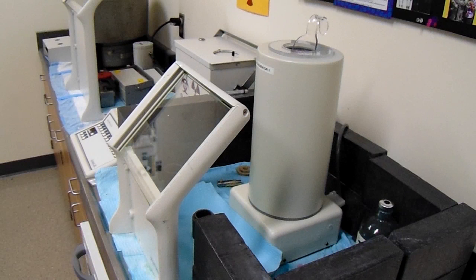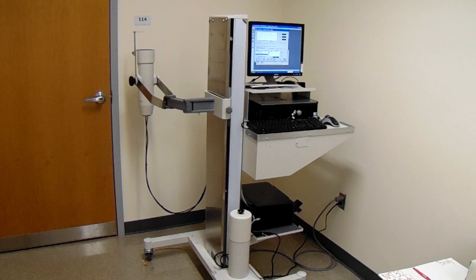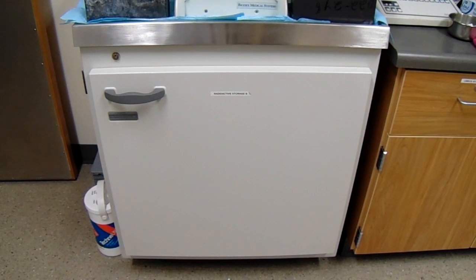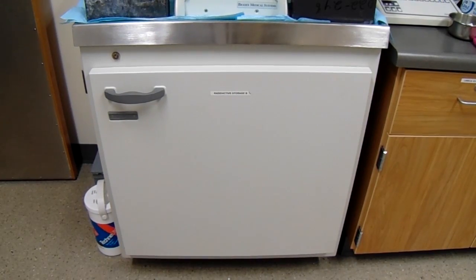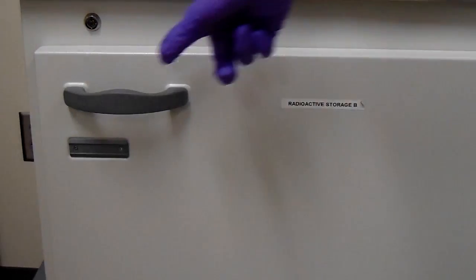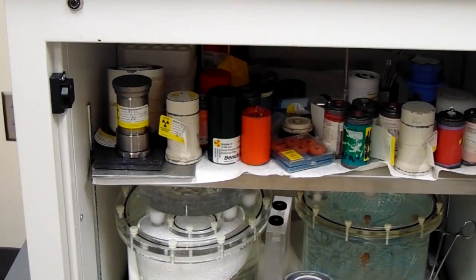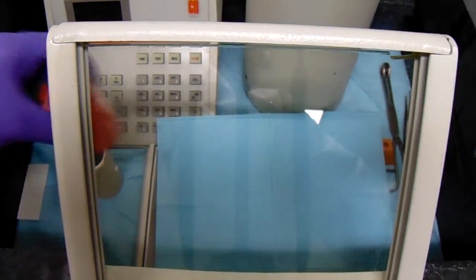Next, we're going to move on to equipment quality control. As far as equipment goes, we're going to have our calibrators and our well counter. Now, in order to do any QC on this equipment, we're going to need our cesium sources to check to see if the equipment is still in working order. Now, the reason we use cesium to check our equipment is because it has a really long half-life of 30 years, so that we know the radioactivity in the source from when we got it is going to be pretty close to the same all the time.